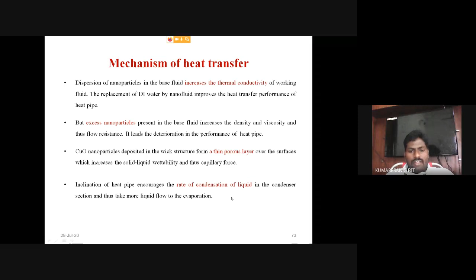Okay, so if you are tilting the heat pipe towards the vertical position, then the contact of the working fluid with the surface area of the condenser section will increase. Then automatically the rate of heat transfer from the condenser section also increases. Thus, more liquid flows to the evaporator section.